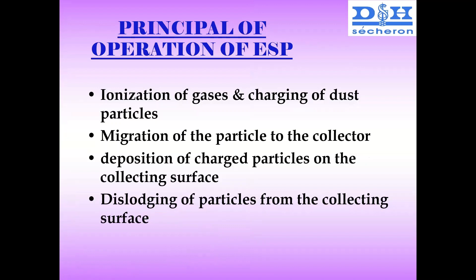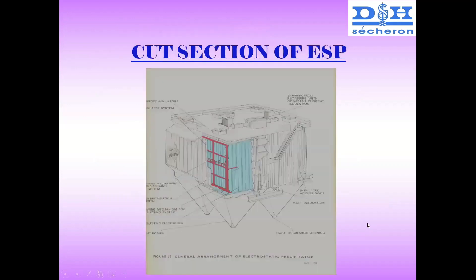To understand the principle of operation of ESP: ionization of gases and charging of dust particles, migration of the particle to the collector, deposition of charged particles on the collection surface, and dislodging of particles from the collecting surface. ESP stands for electrostatic precipitator — whatever ash in dust form is being taken by the ID fan towards the chimney passes through ESP filters, so that dust particles are held and as much clean air as possible passes through the ESP outlet to the chimney.